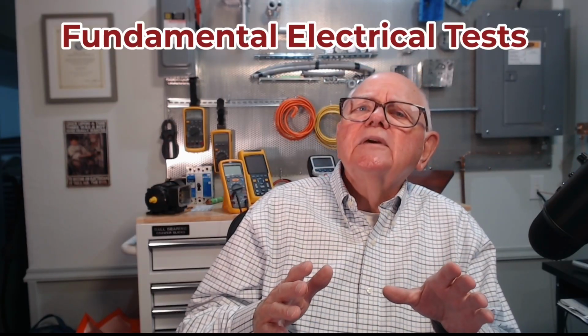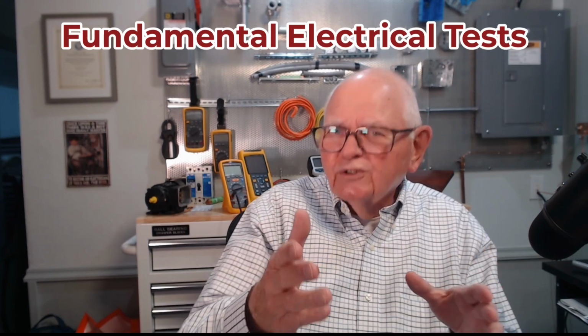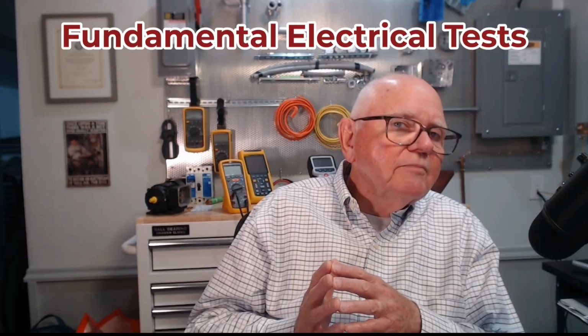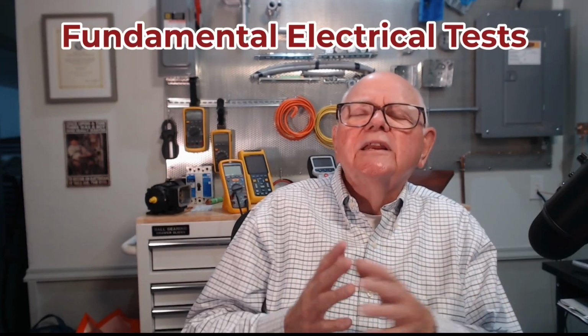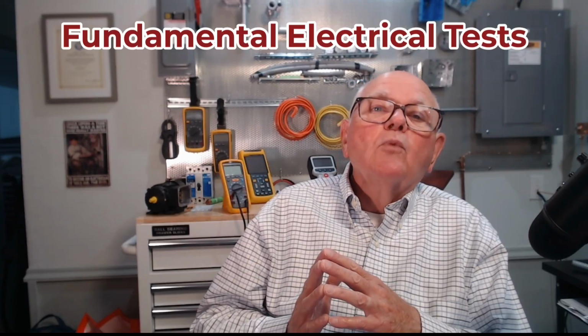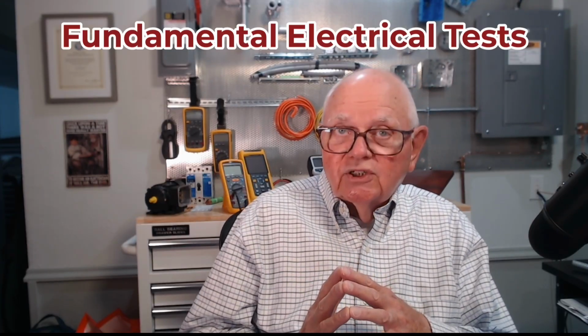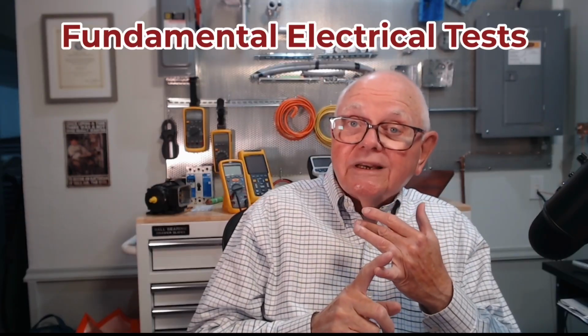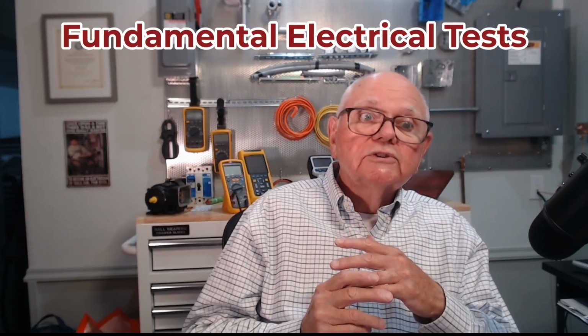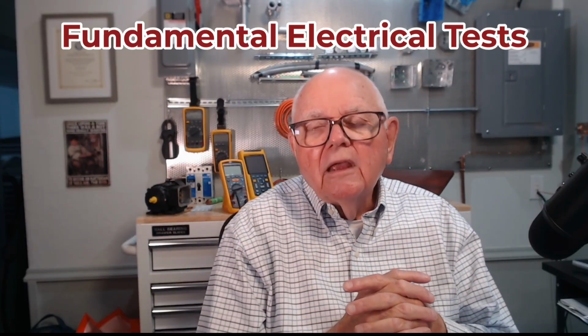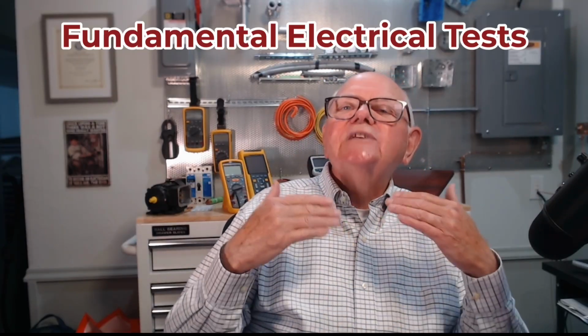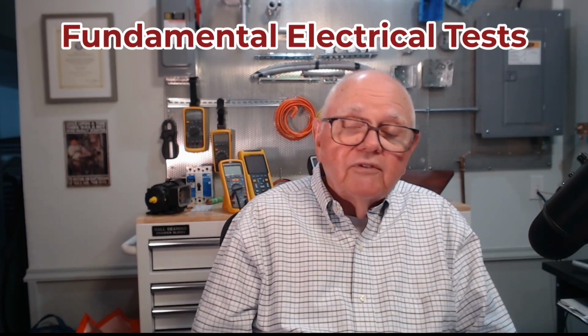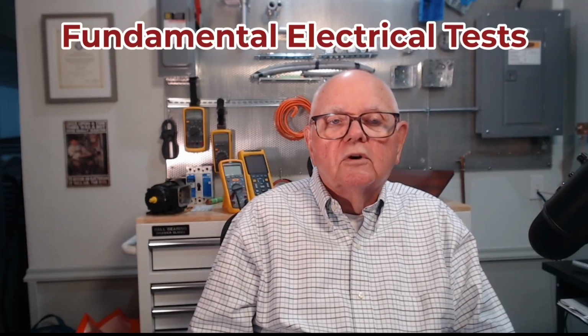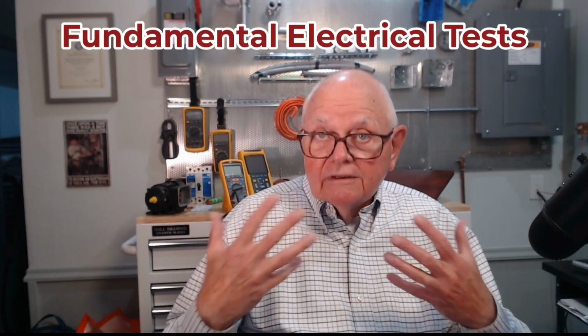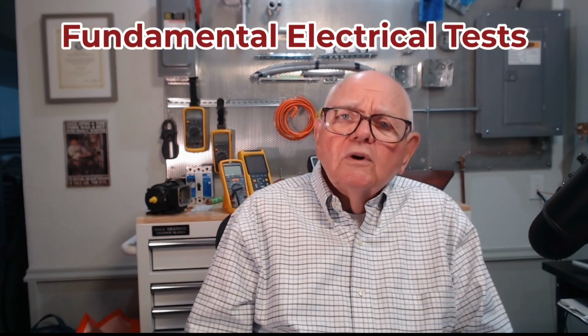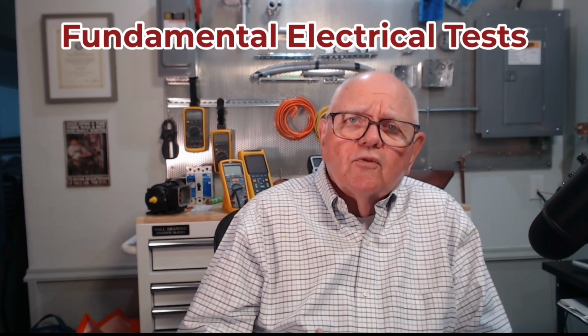Well, NFPA 70B helps you to decide what electrical equipment you need to do maintenance on, and there are tables in NFPA 70B that can help you with that. Then once you decide what equipment you have to do maintenance on, the next question would be, what maintenance do you want me to do, and how often do you want me to do it? And of course, the correct answer is, well, it depends, right? So NFPA 70B helps you to set up that electrical maintenance program, which you're required to have anymore. It's required to be in writing, documented, in other words, for electrical equipment that you deem needs to be maintained.